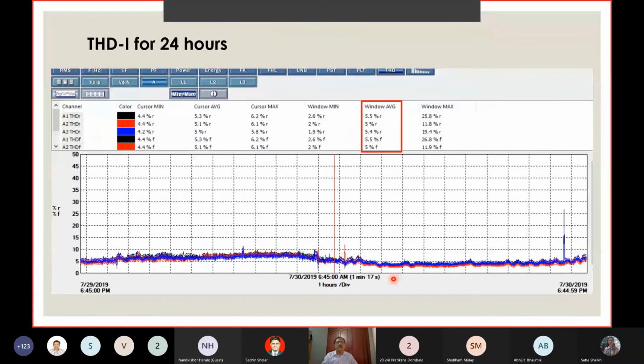voltage swell also. This is the harmonic THD. Now the tool which I am using is not class A and it does not measure TDD, it measures THD. It's possible for me to calculate using an Excel, because this THD is with the denominator fundamental current. But if I know the load current for that day, then I can use the average load current to work out this TDD value. It is possible for me to calculate the TDD side by side against the THD values. Whereas in the Fluke 438 or 435-2 class A, which Sachin Shelar has, it is possible to directly measure the TDD values. The limits are mentioned under TDD, therefore one has to be very careful about using the limits properly and interpreting them.